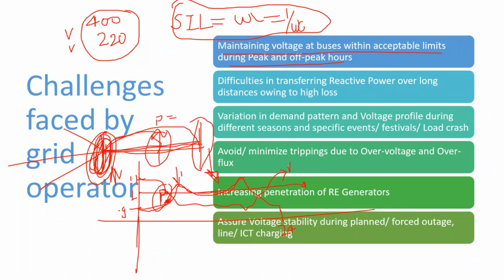Okay. So what is happening is that as the reactive power and active power are changing in the system at different operating points throughout the day, the voltage of that node, the substation node or the terminal node, is also varying a lot. And due to that, for equipment safety and all these safety aspects, as well as to operate within the transmission line limit and to safeguard the entire system, you have to maintain this voltage within the limit. So there are operational limits defined in which you have to maintain the voltage. That is the job of the grid operator.